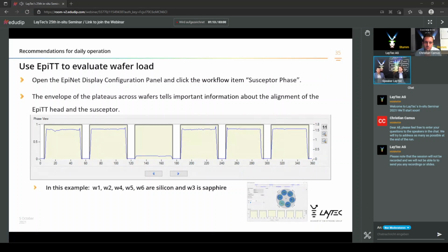What will also help in the software is to make a scan over the full revolution of the susceptor. You should use the EpiNet display configuration panel, and you click on the workflow item susceptor phase. EpiNet software will scan all the wafers. And if all wafers are the same, we would expect a rectangular shape reflectance envelope. In that example, we inserted a different substrate, one is a sapphire wafer. Sapphire has a much lower reflection than silicon. So you see immediately that something is wrong on the third pocket.